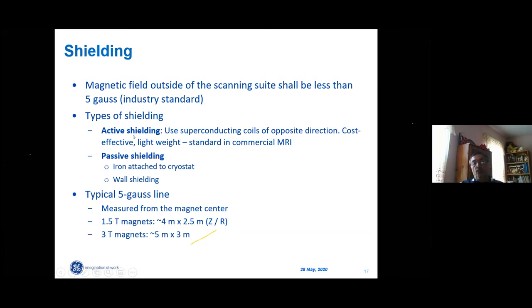So all commercial MRI magnets today use active shielding with shield coils in opposite direction. And we measure it with the 5 Gauss line. Why 5 Gauss? This is safe to any patient, even with a pacemaker. So typical field requirements are 4 meters in axial direction and 2.5 meters in radial direction for 1.5 Tesla magnets, and 5 by 3 meters for 3 Tesla magnets.